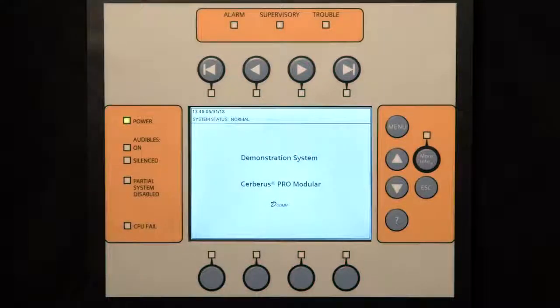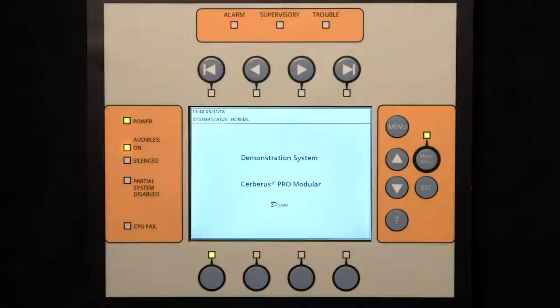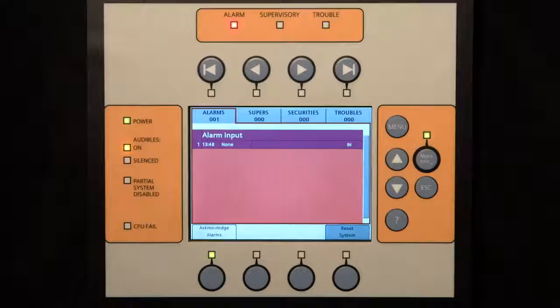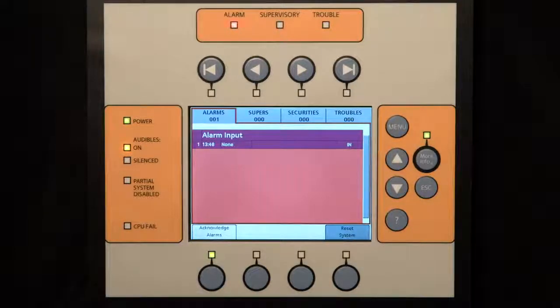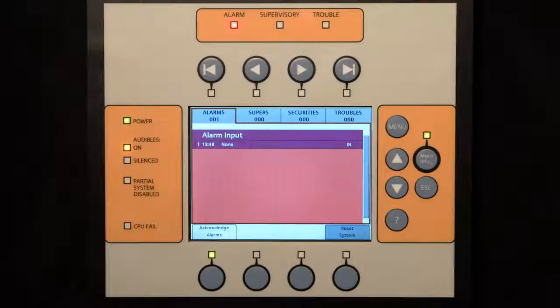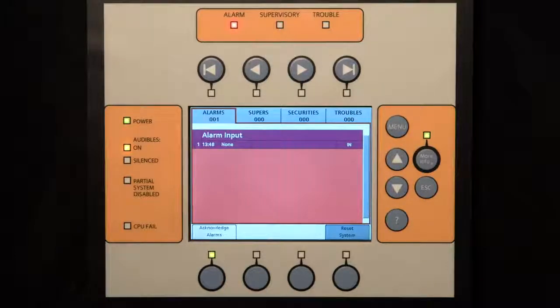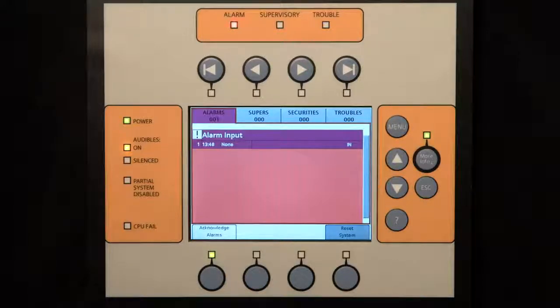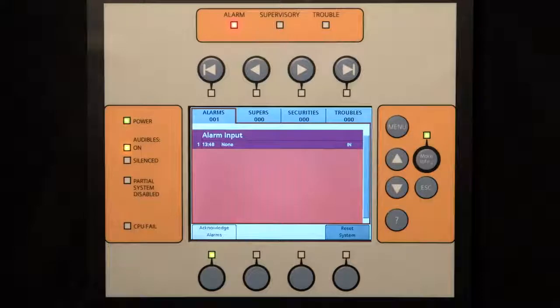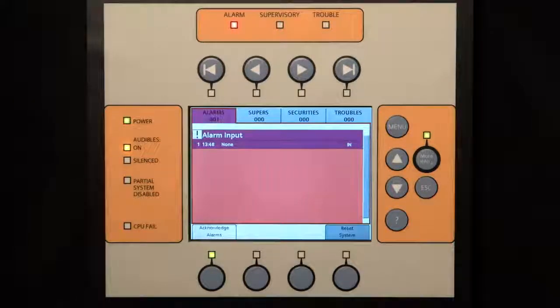When an event occurs in the system, the display automatically enters the alert mode. This alert mode allows the user to see active events and control these events. If an event type is an alarm, trouble, or a supervisory, the appropriate LED blinks and may cause the notification appliances to sound and the audibles to play messages throughout the building. The internal buzzer sounds and the tab on the display for the corresponding event queue flashes.